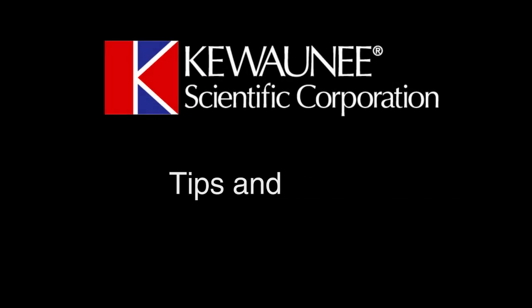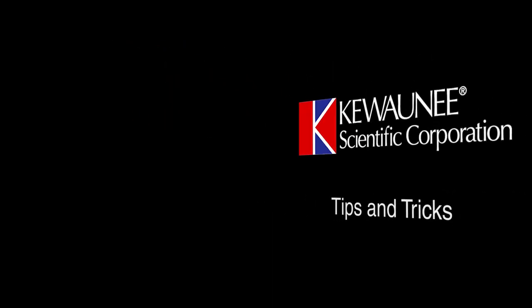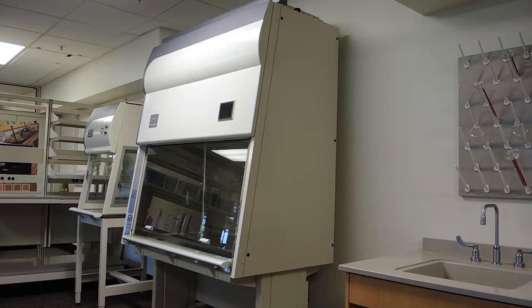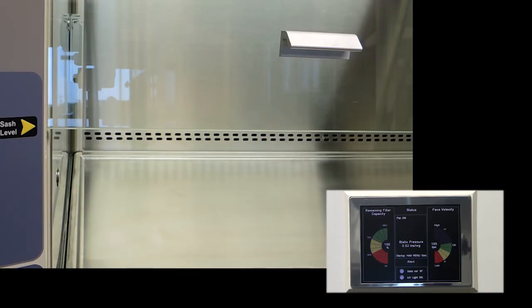This is Kewaunee Scientific Tips and Tricks. This video covers adjusting micro switches on our Interceptor biological safety cabinets that were manufactured between March 2013 and October 2016. These switches monitor the sash position and trigger an alarm when the sash is not in the correct position.